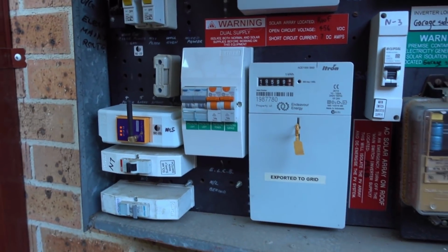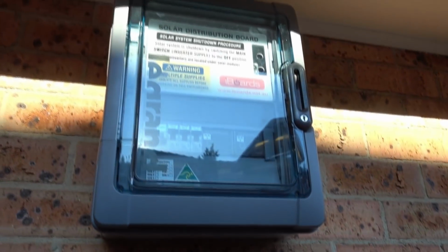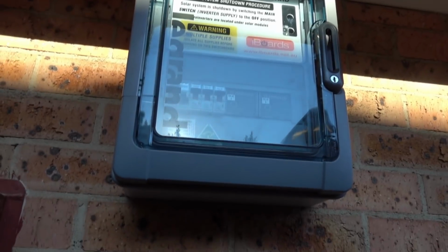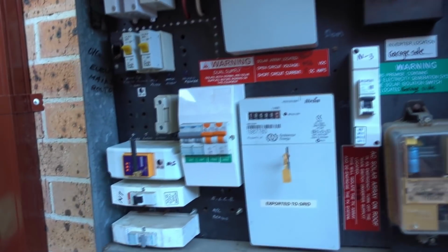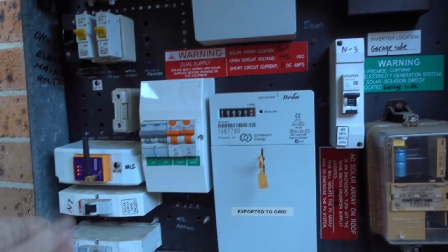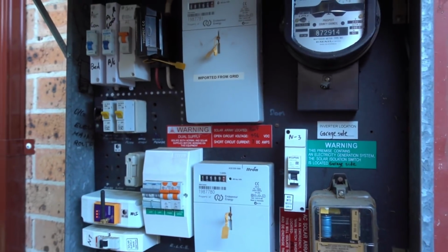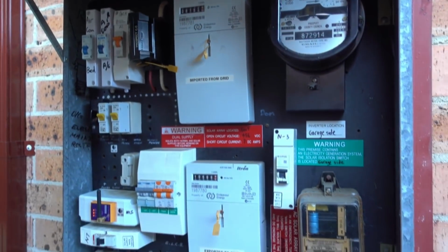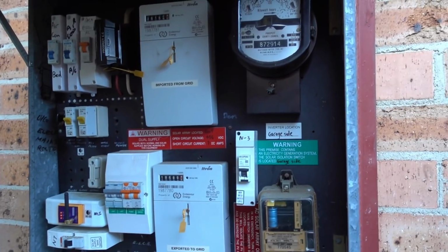So it's measuring the total production, and then it's also measuring the consumption based on the main fuse and the main wire up there. So what we want to change is the Enphase Envoy measurement system, which is up in the box there, and it's also got exactly the same, or had the same configuration. It has 2 production transformers in parallel, one for the 5 kilowatt system, one for the 3 kilowatt system, and also the same consumption current transformer up here as well. So we want to actually change just the Envoy system.